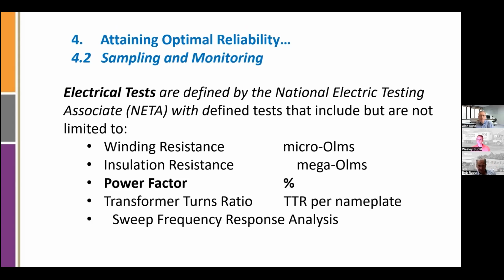That is a fantastic question, because there will be some risk in leaving the transformer to go with higher furans. It could last another 20 years. It's its ability to withstand a fault, and to check that better, electrical testing comes into play. So we do test transformers with elevated furans, electrically test them, and then can more or less say, I think this is worth keeping in service.